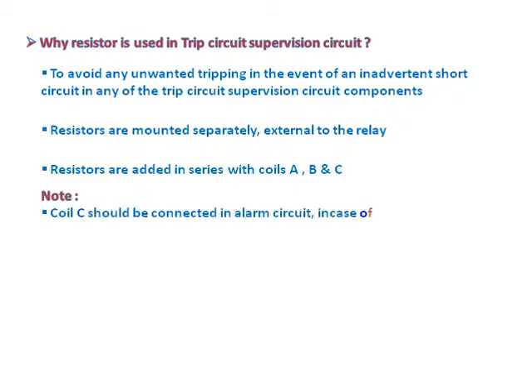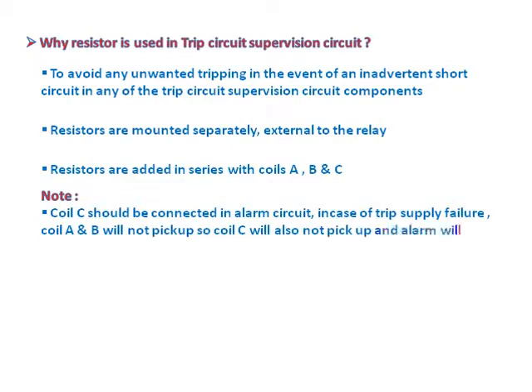Note: Coil C should be connected in the alarm circuit in case of trip supply failure. If coil A and B will not pick up, then coil C will also not pick up, and an alarm will be initiated indicating that the TCS relay is unhealthy.